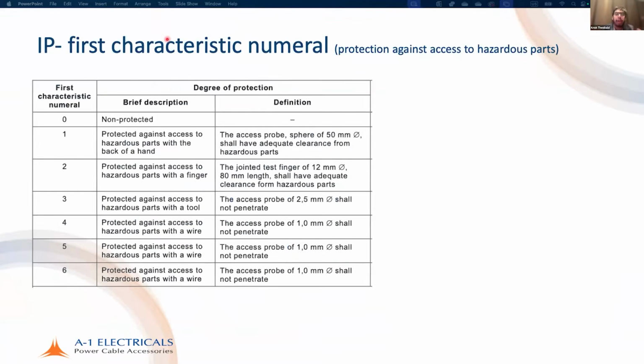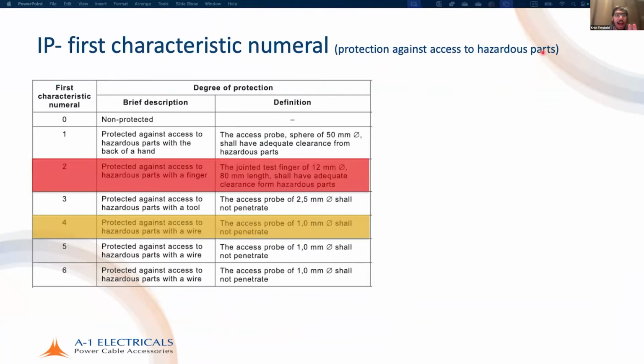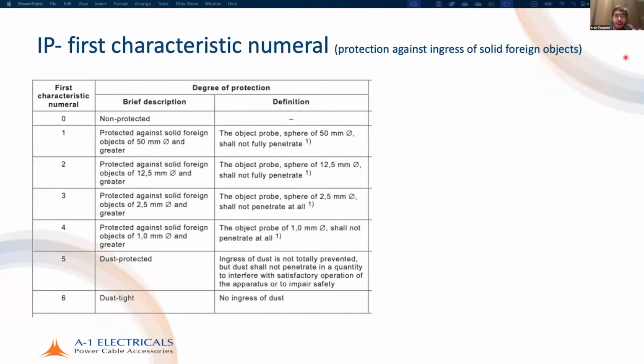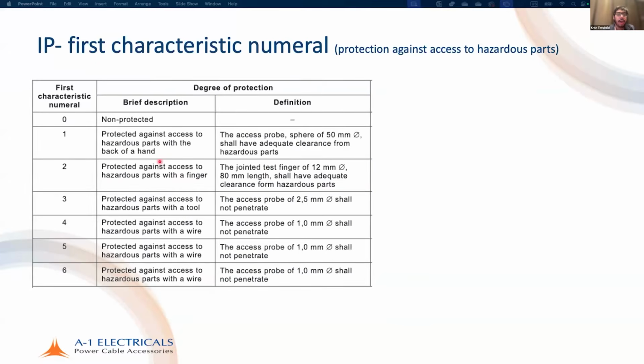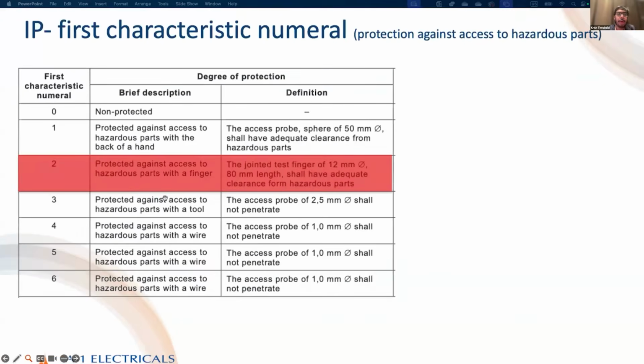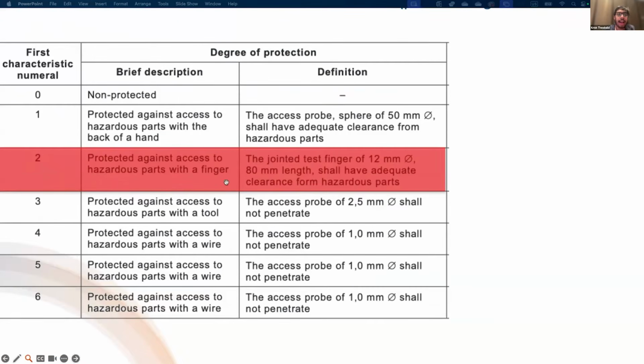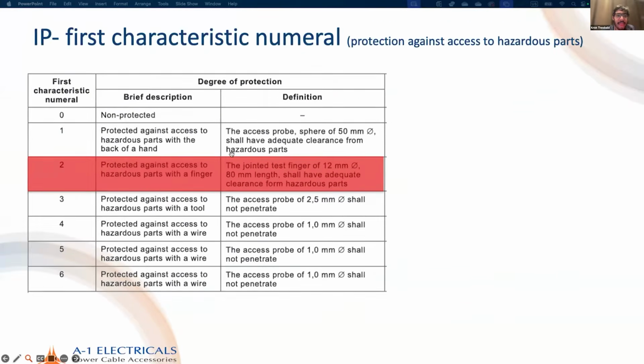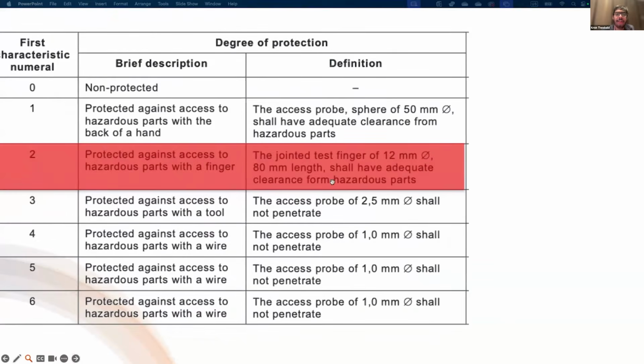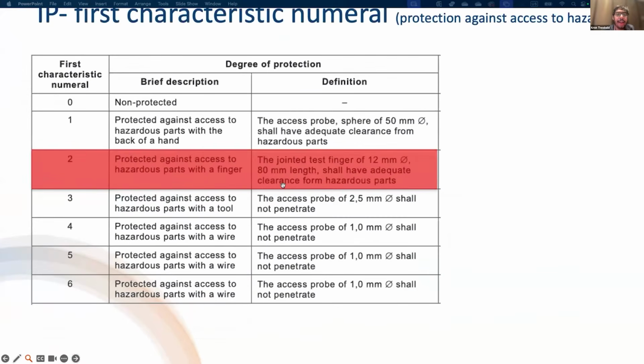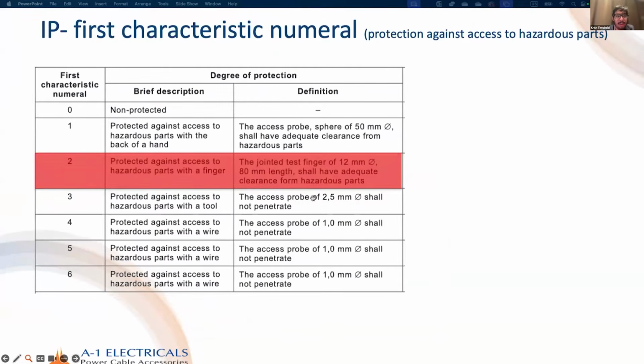Now, what do these numbers mean? The first characteristic numeral in an IP number or IP alphanumeric code indicates two things: protection against access to hazardous parts and protection against ingress of solid foreign objects. So, when we say IP2X, it means that it's protected against access to hazardous parts with a finger, and the test is performed with a test finger of 12 mm diameter by 80 mm length, and there is required to be adequate clearance from any live parts.